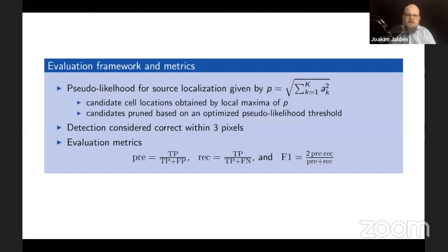Then we have to set the threshold level. So how large should this have to be in order for it to detect a spot? You have to set it slightly above 0 in order to avoid noise in the optimization. But how much? The way that we approached this was looking at how people in the business actually analyze this. Typically you have a sensitivity slider in the software that sets the sensitivity. You calibrate that with respect to your test measurement, you find the level that you're happy with, and then you make a comparison between the two.